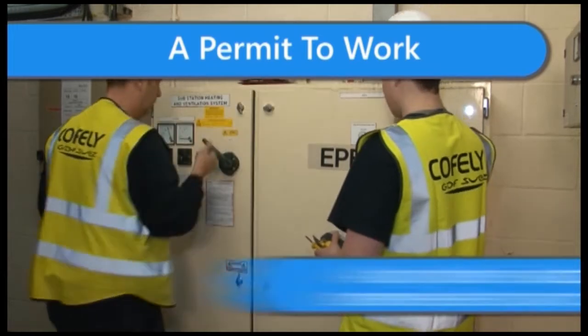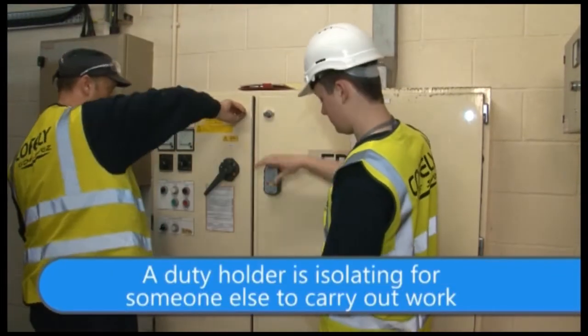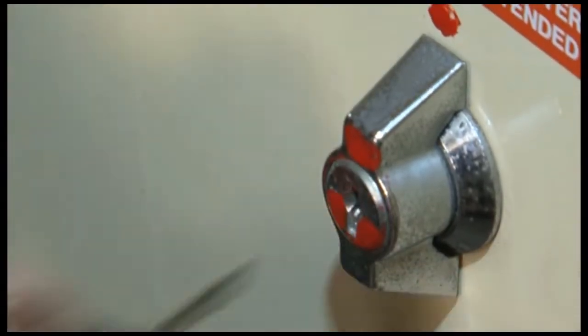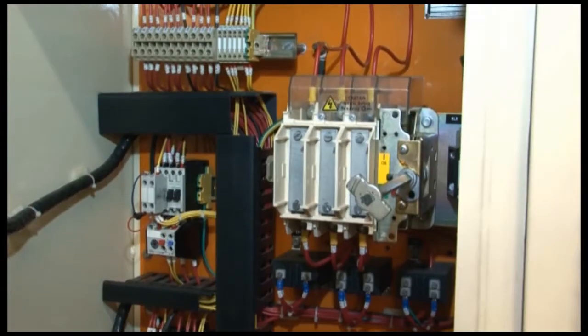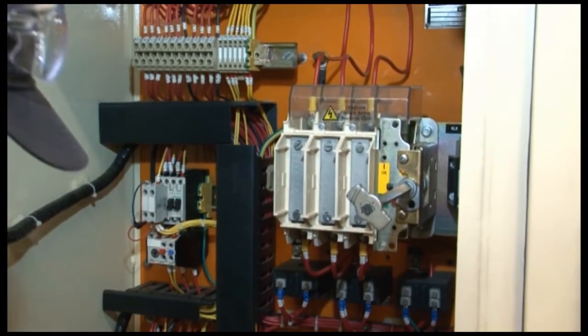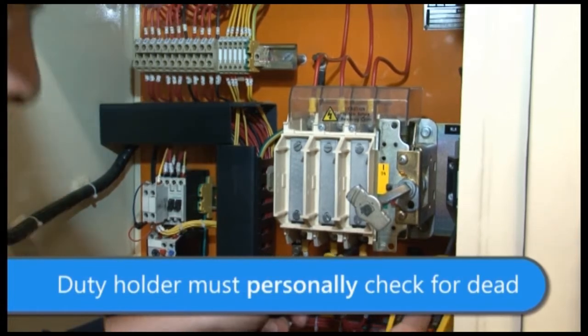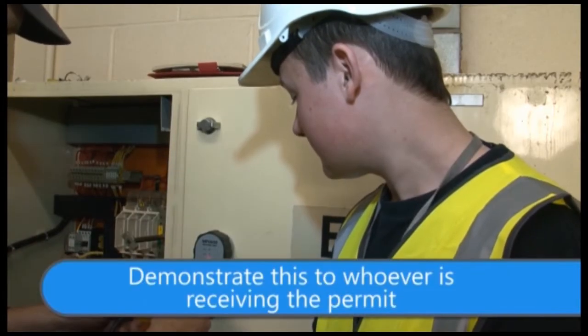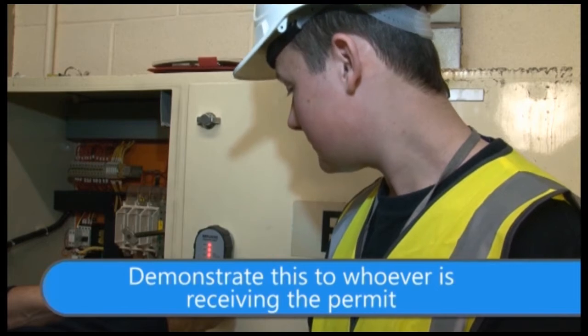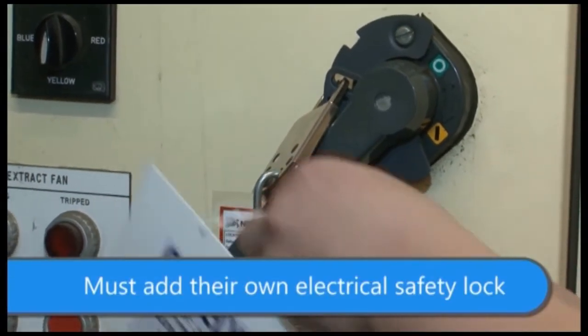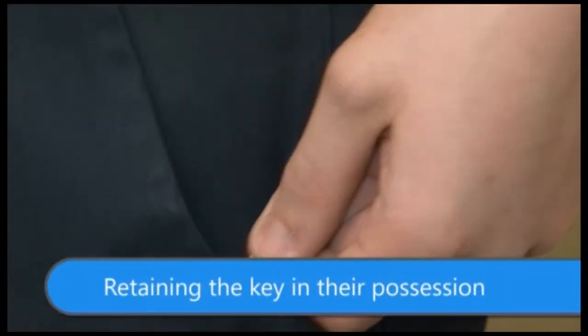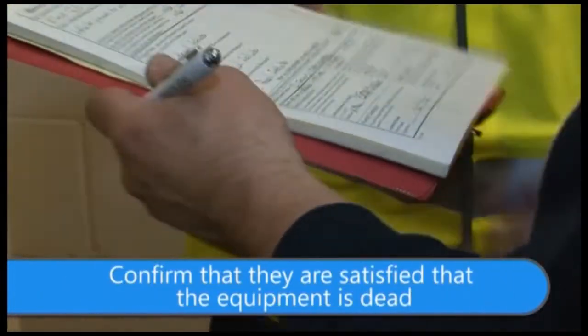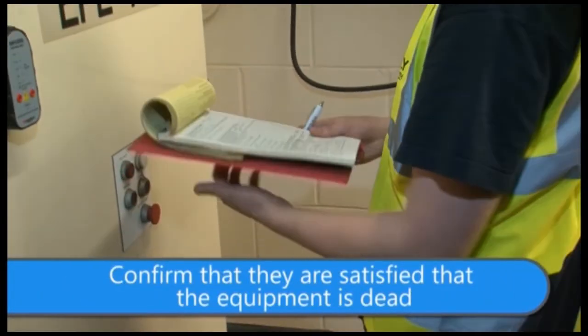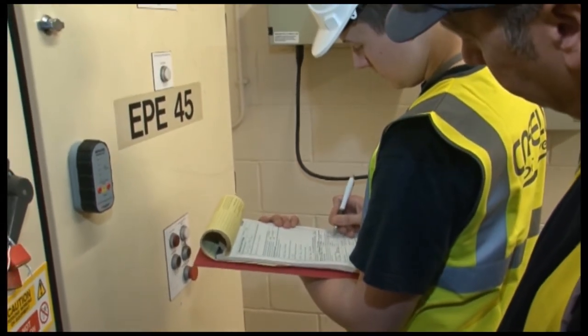Isolations can also be carried out under a permit to work. A permit to work will be issued when a duty holder is isolating for someone else to carry out work. The duty holder must ensure that the isolation procedure is followed as before. However, it is important that the duty holder must personally check for dead, and demonstrate this to whoever is receiving the permit. The receiver of the permit must add their own electrical safety lock, retaining the key in their possession, confirm that they're satisfied the equipment is dead, and that all the precautions are adequate before signing the permit.